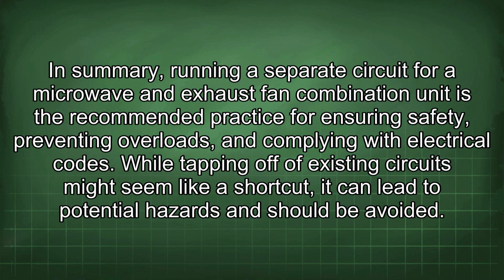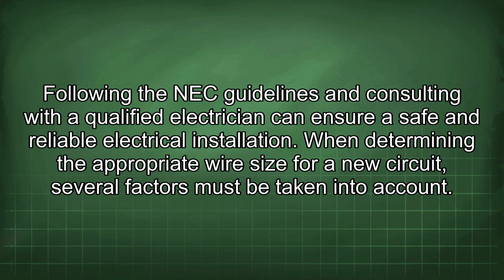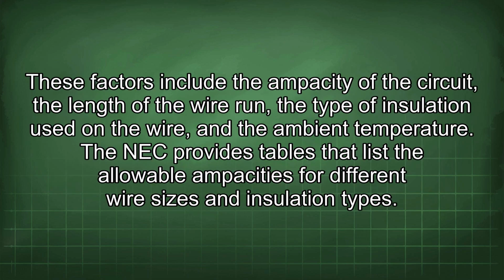While tapping off of existing circuits might seem like a shortcut, it can lead to potential hazards and should be avoided. Following the NEC guidelines and consulting with a qualified electrician can ensure a safe and reliable electrical installation. When determining the appropriate wire size for a new circuit, several factors must be taken into account. These factors include the ampacity of the circuit, the length of the wire run, the type of insulation used in the wire, and the ambient temperature.